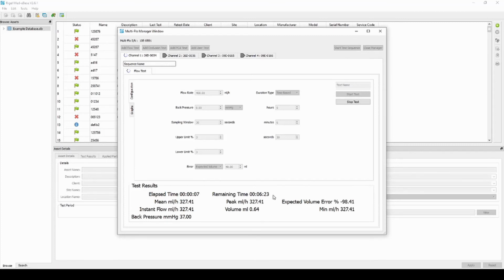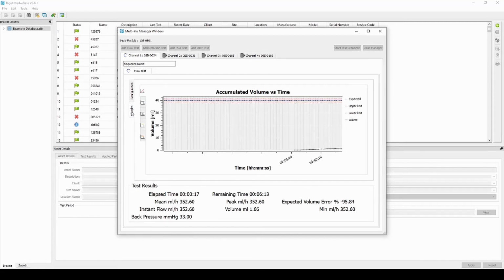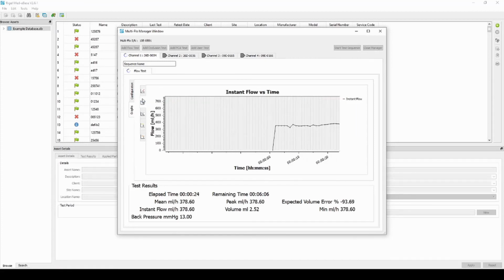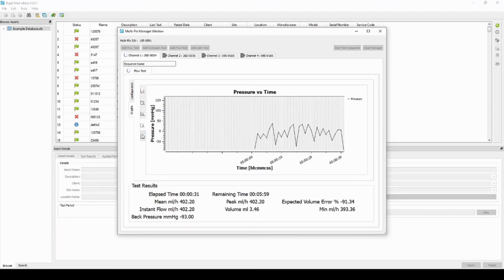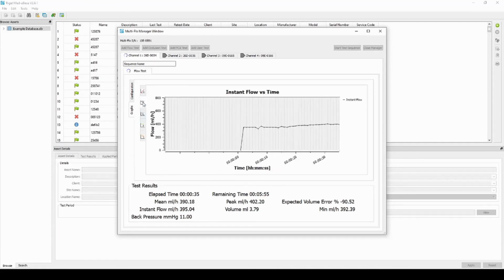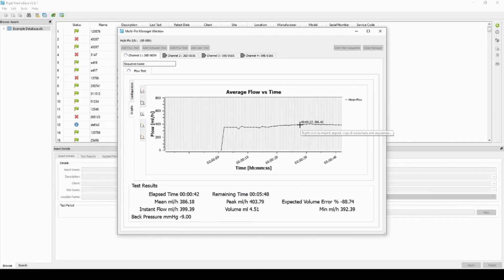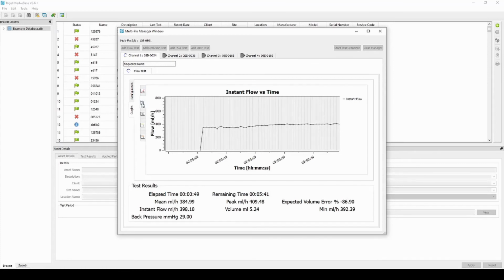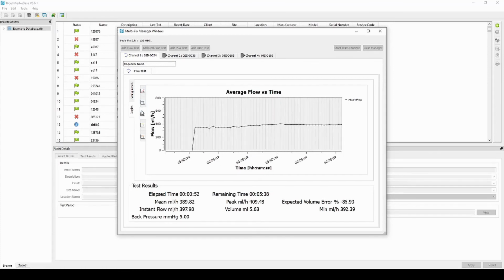Now the time's elapsing, and with this you've got a similar display to the Multi-Flo, but it goes a little bit more in depth. So you've got all these graphs, but you can analyse the expected limits, and also the upper and lower limits from whatever you've set your limit type to. And also you can select individual points at times, and you can get those values at that specific time. So it's a way of really extracting the data and playing around with it as much as you need to, really. You can also right click to inspect different parts of the graph. So really useful piece of software when it comes to the Multi-Flo.